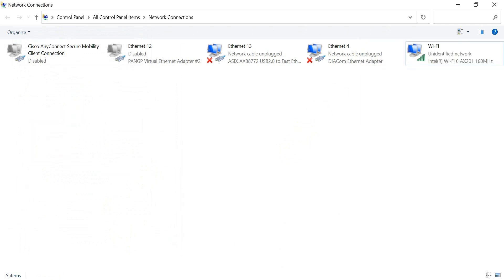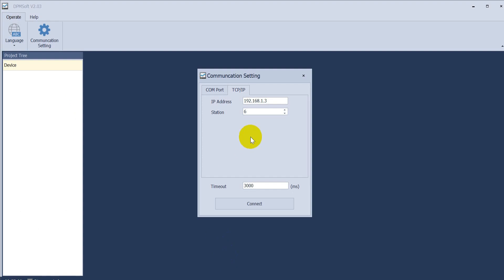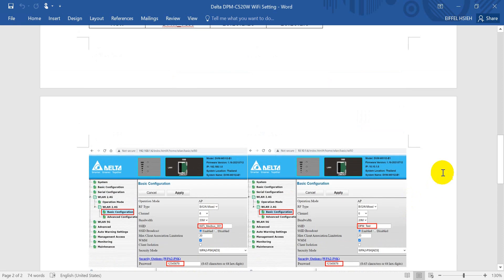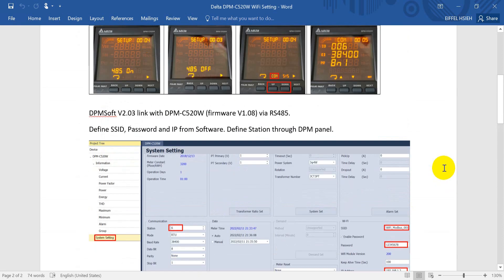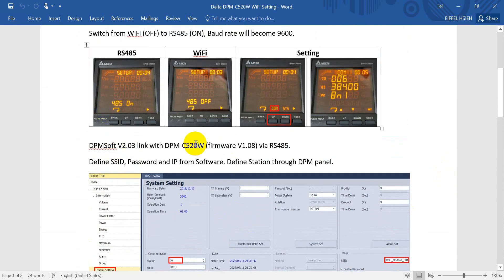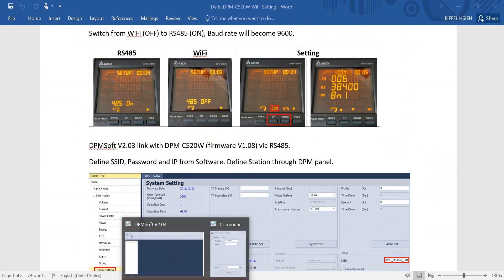Next step, we will use DPMSoft to connect via TCP. I want to remind one thing: because at the beginning we used RS-485 to access the power meter, we had switched it to on. Now that we want to use the Wi-Fi function, remember to switch the function back to off. Otherwise you cannot access.